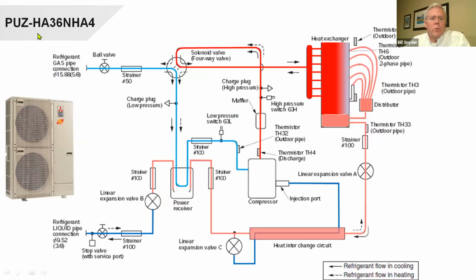This is a PUZ-HA. HA would indicate that it's also a hyperheat. So there's a 3-ton P series. Very, very similar. Here's a compressor. We come out of the compressor. There's a thermistor and a muffler. We come through the reversing valve to the outdoor unit. You've got an outdoor entering pipe thermistor, a heat exchanger thermistor, an outdoor temperature thermistor, and there's the outdoor pipe temperature thermistor and a leaving pipe temperature thermistor.